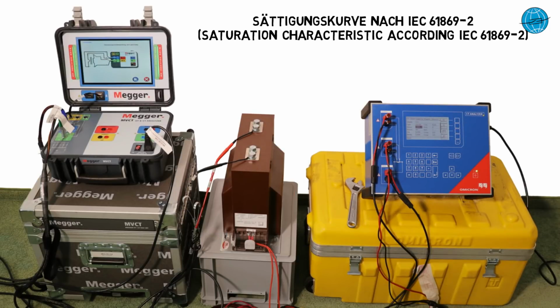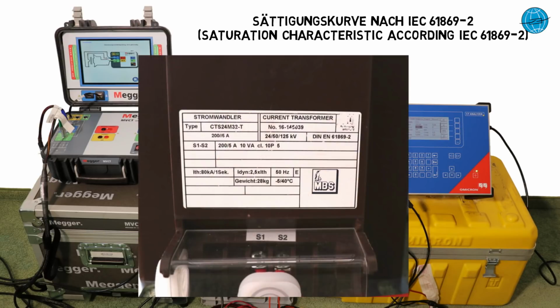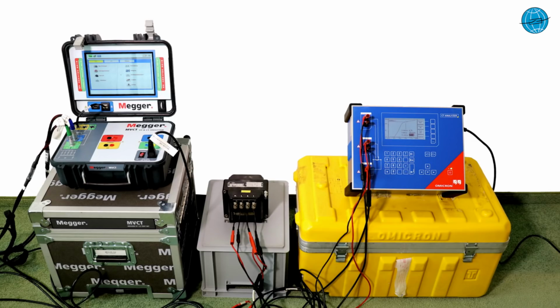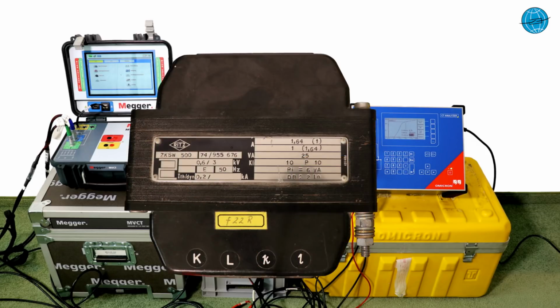A 10P5 current transformer with a nominal ratio of 200 to 5 amps with a power of 10 VA. Our second CT is an old 10P10 starting CT. It has an exotic nominal transmission ratio of 1.64 amps to 1 amp and it's quite strong with 25 VA.